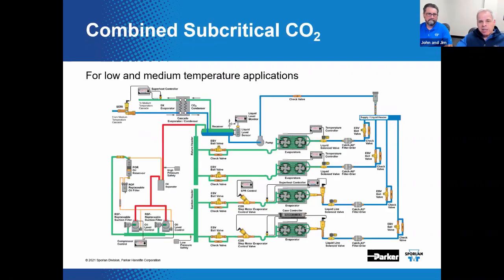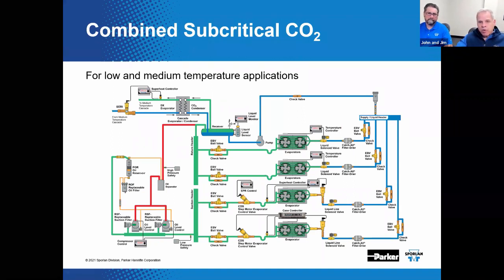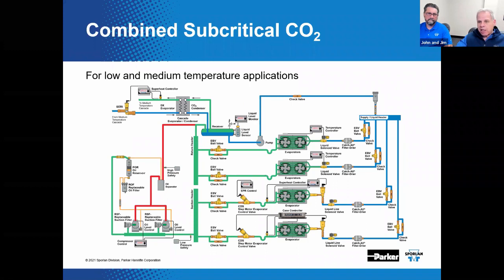The combined subcritical CO2 system is commonly used when a supermarket wants to take the use of CO2 one step further. The only difference between this and what we have already covered is that liquid overfeed and cascade are operated from the same platform. The CO2 is pumped both to the liquid overfeed portion and the cascade portion. This being, I presume, the overfeed portion. There's a pump over here. And this being the cascade portion, we see compressor banks over here.